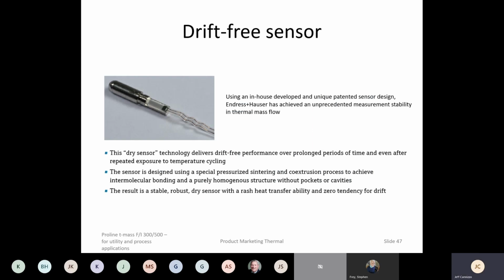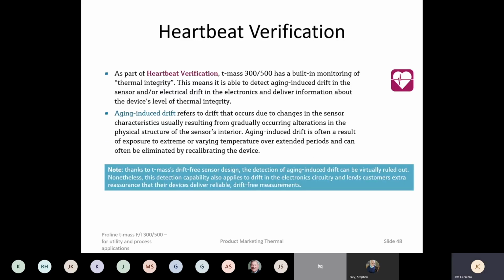Remember, a thermal mass meter is basically measuring temperature. So your RTDs can wear out, they can get moisture causes drift, etc. The temperature expansion and contraction can cause the RTDs to fail. So we've developed a drift-free sensor, and it's a dry sensor. So it really limits the expansion and contraction of the sensor due to the temperature changes. And of course, it has heartbeat verification, which, as I said, is basically a built-in program for monitoring the accuracy, the condition, the life of the meter, how it's aging.